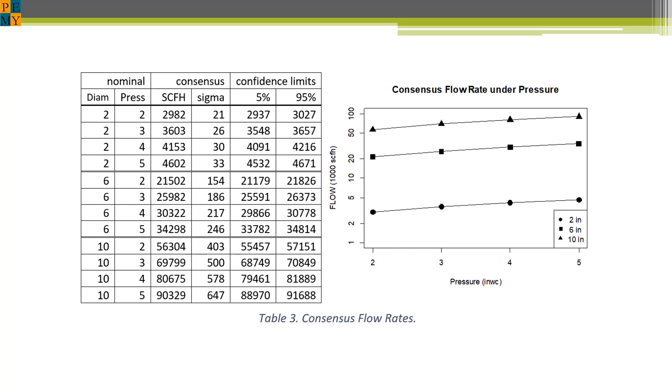Of course, if the vendors are significantly different, then at least one of them must be inaccurate. So we are in a position of determining whether the vendors agree with one another within the margin of statistical error, but we cannot say which of them deviate significantly from the true gold standard flow rate. Using gold standards for testing along with a more appropriate testing protocol is a follow-up item if API decides to move forward to correct these flow measurement problems.